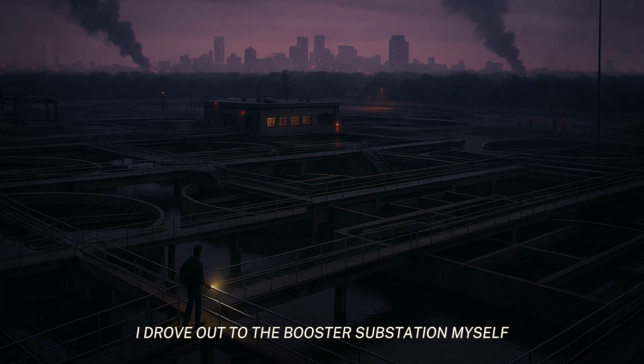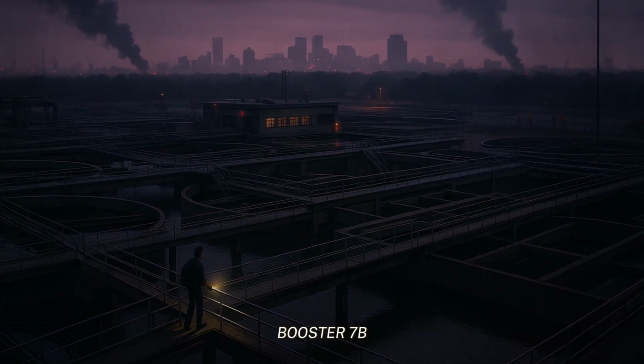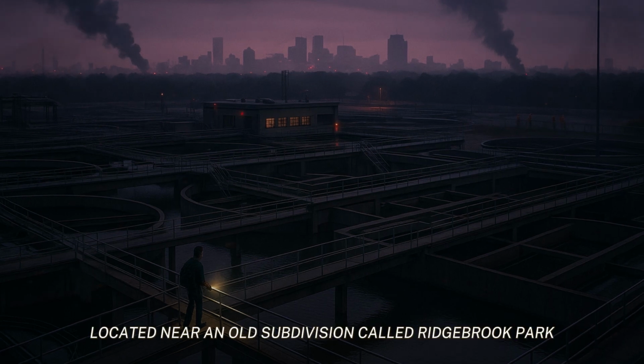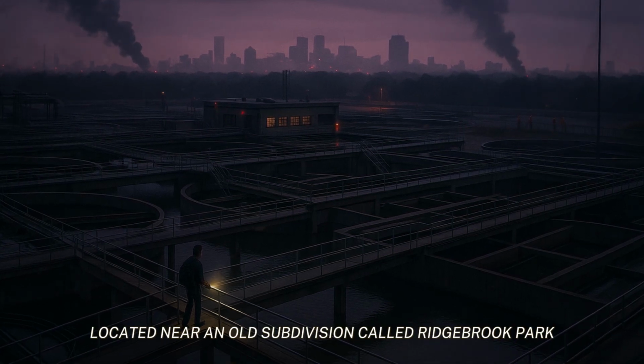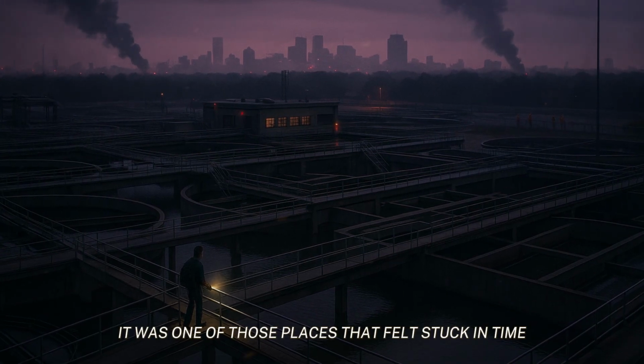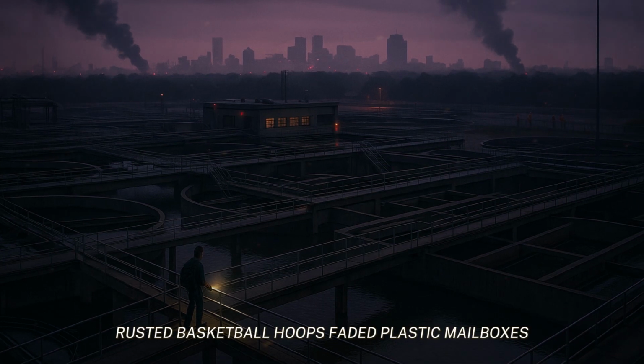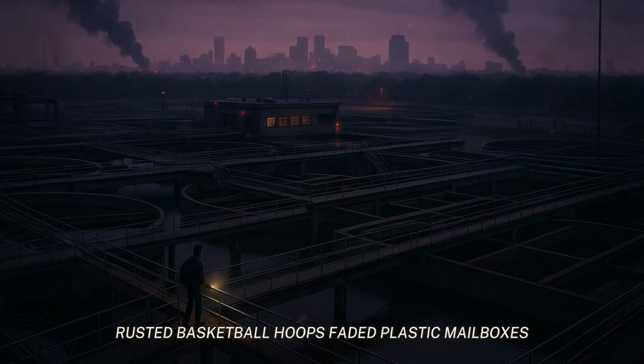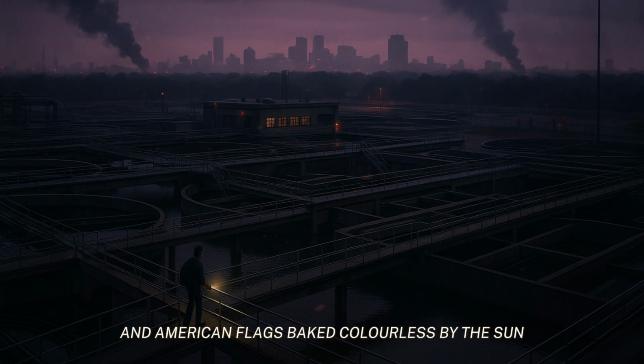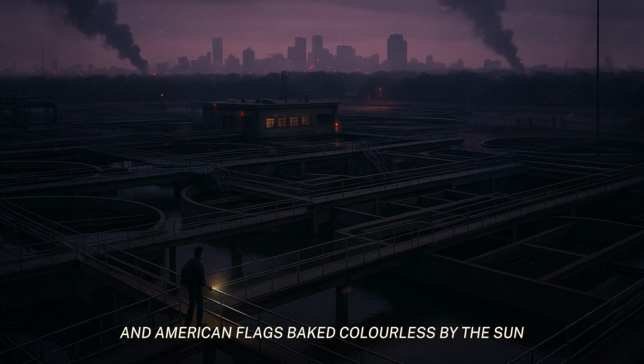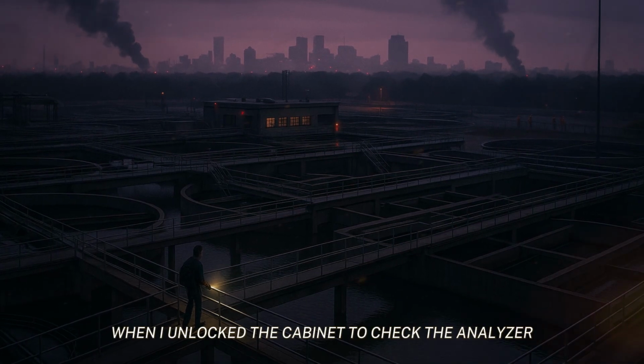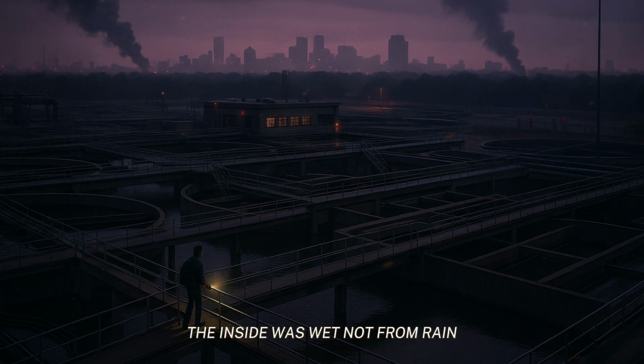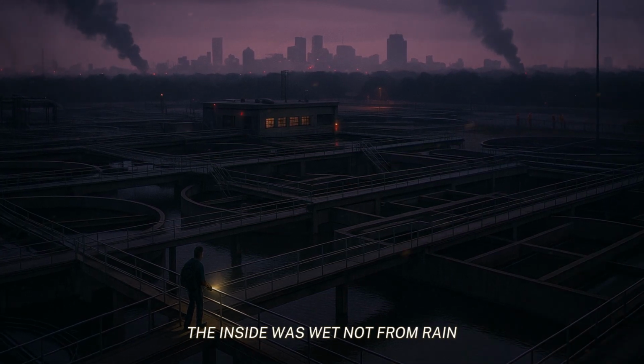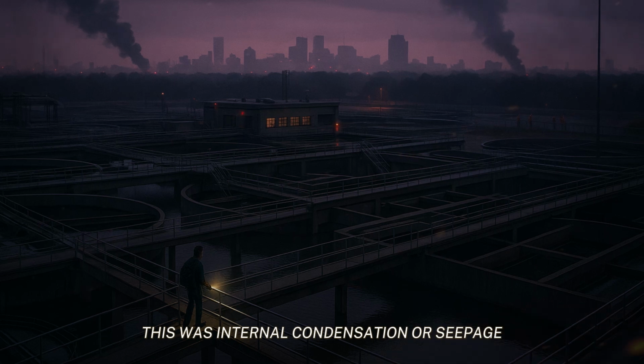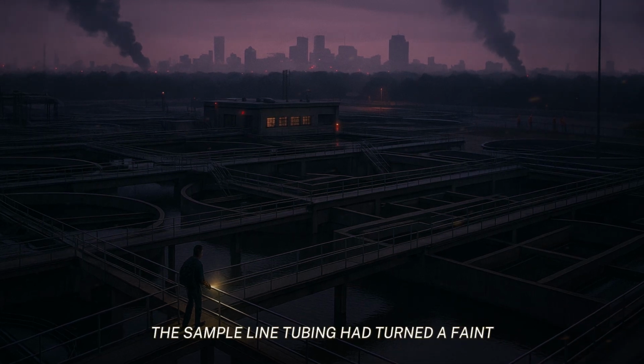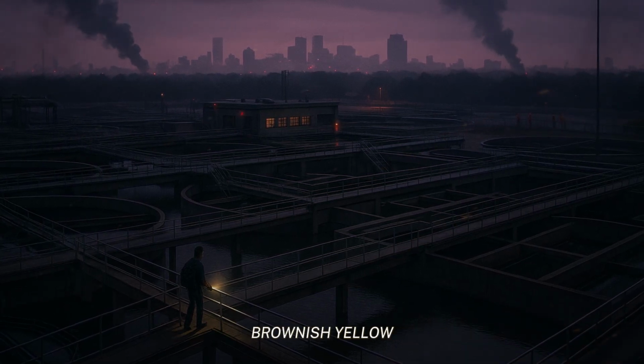I drove out to the booster substation myself, Booster 7B, located near an old subdivision called Ridgebrook Park. It was one of those places that felt stuck in time: rusted basketball hoops, faded plastic mailboxes, and American flags baked colorless by the sun. When I unlocked the cabinet to check the analyzer, the inside was wet. Not from rain. This was internal, condensation or seepage. The sample line tubing had turned a faint brownish yellow.